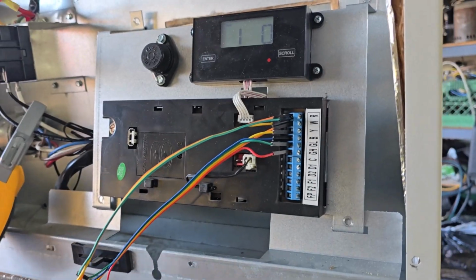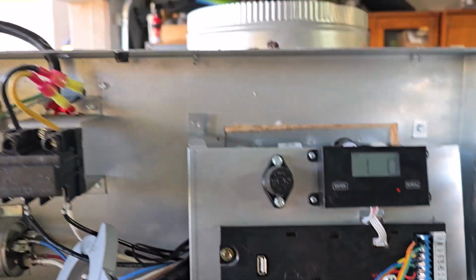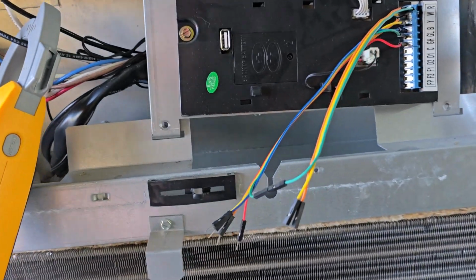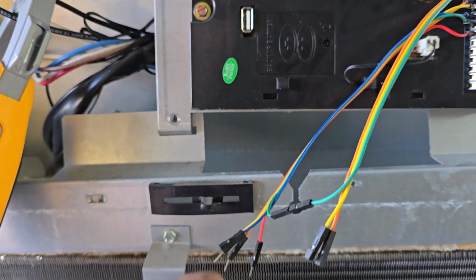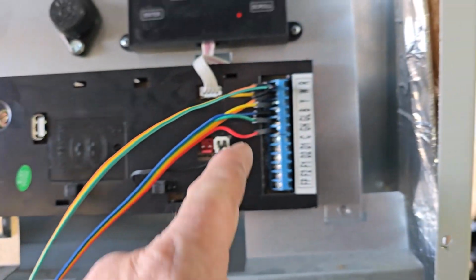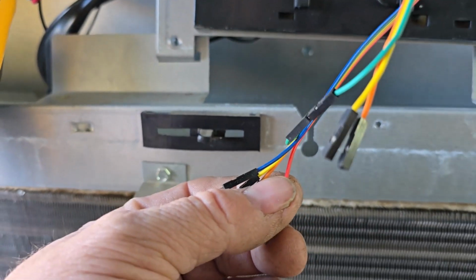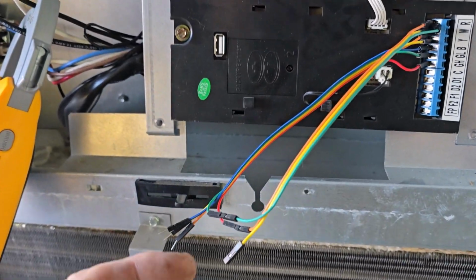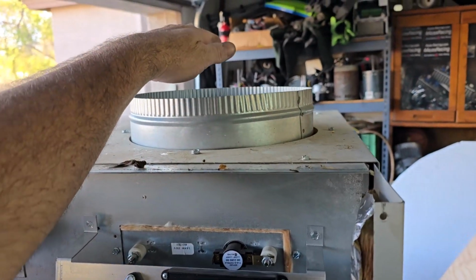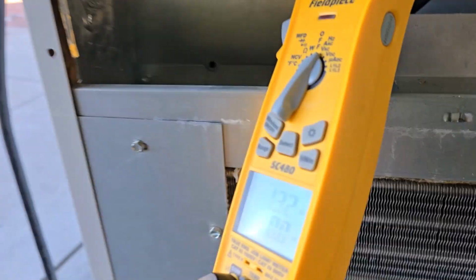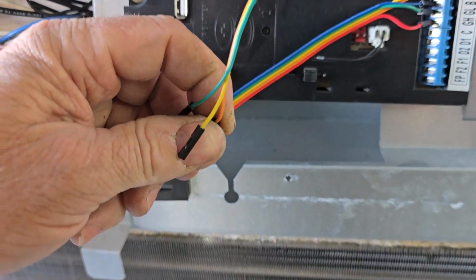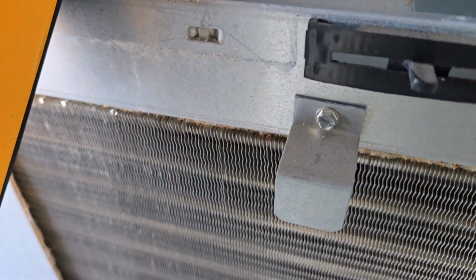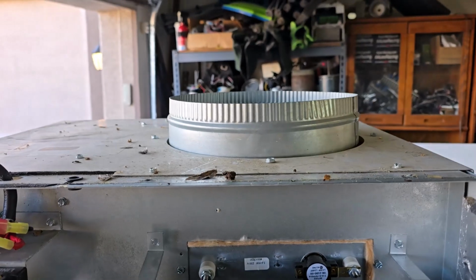I put some little test jumpers on there just to run the unit. It actually did kick the fan on, even with the voltage the way it is. I got it on low. And for high, what do I have? I got the red. Heard the relay kick over. It just pulls a little more power, but it isn't blowing much harder because there's no static on there, so it doesn't really need it. Should go back to low there. There we go. The motor sounds a little better now.